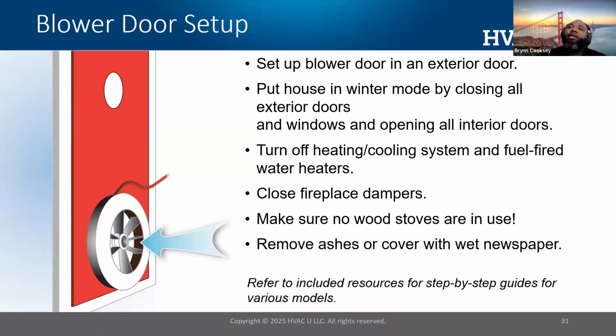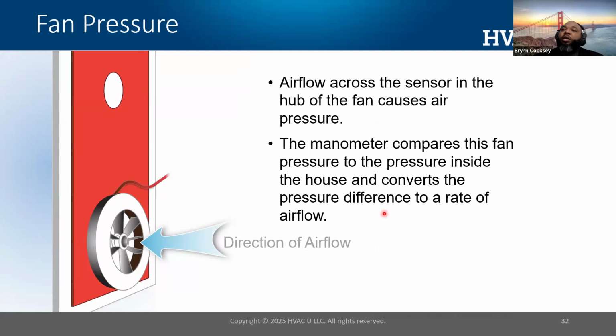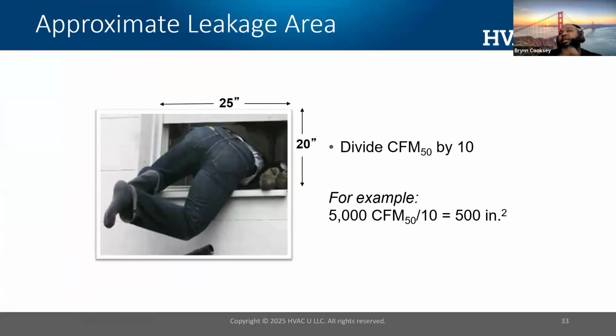When we go to set the blower door up, we're going to set it up in any exterior door. We're going to put the house in wintertime conditions by closing all exterior doors outside of the one that we're using. We're going to disable our heating and cooling systems. We're going to close any fireplace dampers. We're going to extinguish any fires and maybe let them cool and cover the ashes with wet newspaper so we don't bring ashes back into our space. And we're going to run our blower door. And when we run our blower door, it is going to push air out of the building shell, and that air is going to come back through the gaps, cracks, and holes in our building shell, and our pressure gauge is going to help calculate how leaky that structure is. And it's pretty powerful and important. Let's take a look at the data that the blower door gives you. So remember, blower door readings are given in CFM 50, cubic feet per minute, or basketballs of air at 50 pascals.